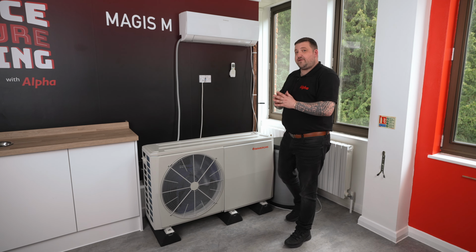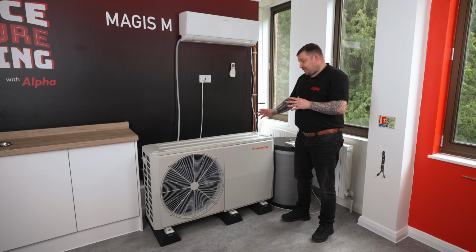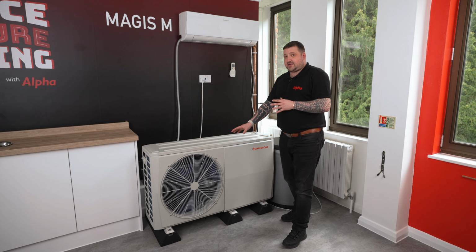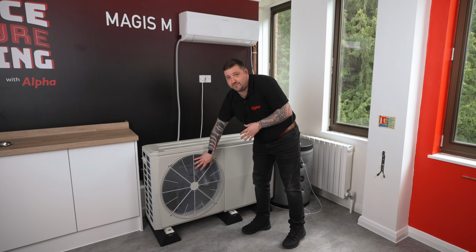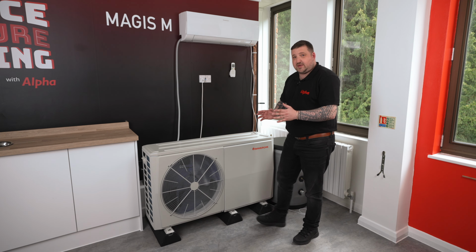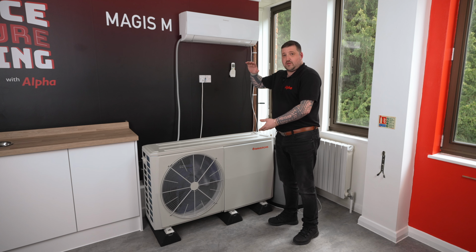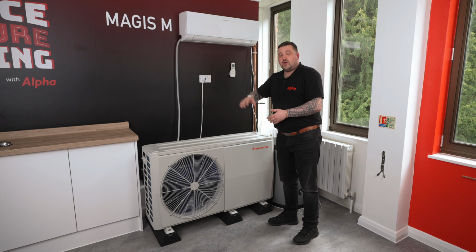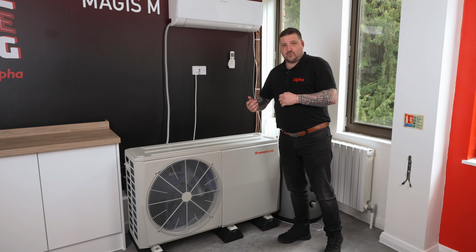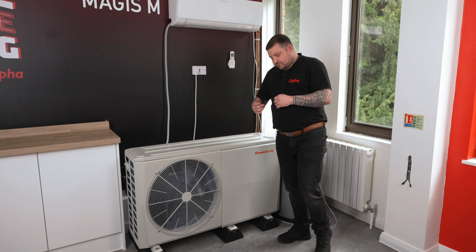They all come in single phase, and the great thing about this unit, getting up to 16 kilowatts, is we've only got one fan. Sometimes when you see 16 kilowatt units, it's like the tombstones, and it's the 2 fans on top of each other. We then go up to 30 kilowatts, which is then 3 phase.